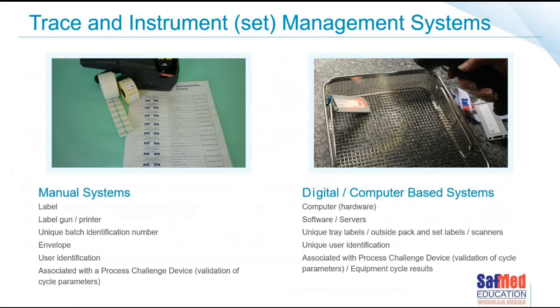Generally speaking there are two main types of tracking and tracing systems: manual systems and digital computerized systems. Manual systems consist of label guns, printers, envelopes, some form of user identification, and all of this needs to be associated with the process challenge device to validate sterilization cycle parameters. Digital computerized systems need a computer, hardware, software, data storage, a way to uniquely identify the tray, a label on the outside, a scanner, and unique user identification — again associated with the process challenge devices.